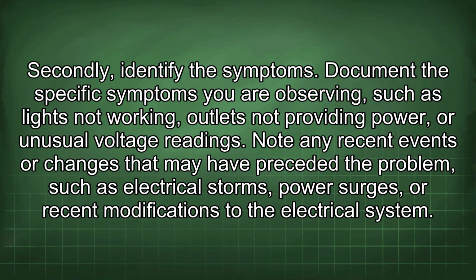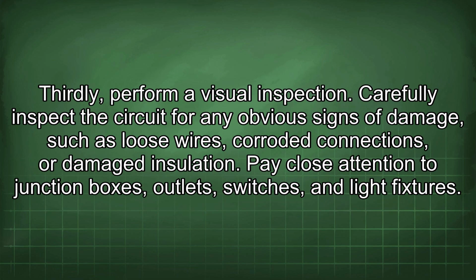Secondly, identify the symptoms. Document the specific symptoms you are observing, such as lights not working, outlets not providing power, or unusual voltage readings. Note any recent events or changes that may have preceded the problem, such as electrical storms, power surges, or recent modifications to the electrical system. Thirdly, perform a visual inspection. Carefully inspect the circuit for any obvious signs of damage, such as loose wires, corroded connections, or damaged insulation. Pay close attention to junction boxes, outlets, switches, and light fixtures.